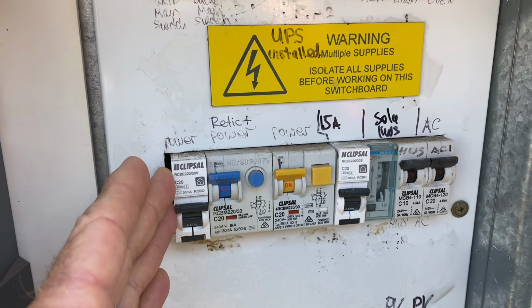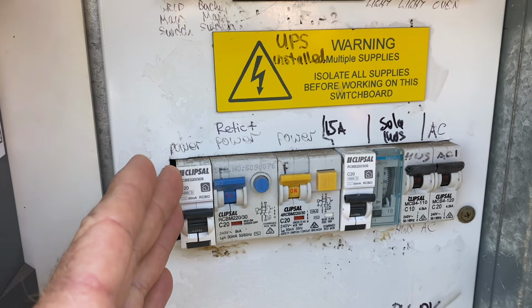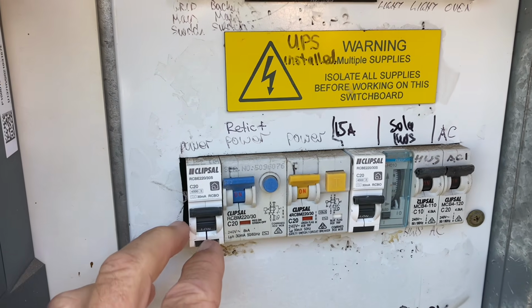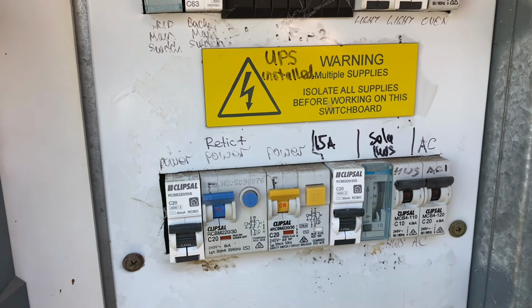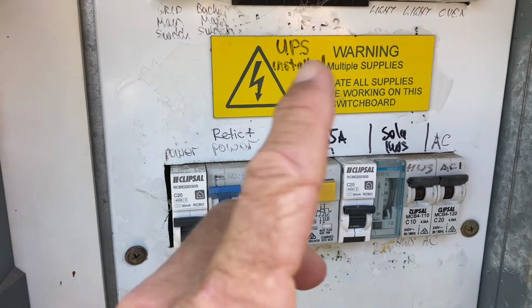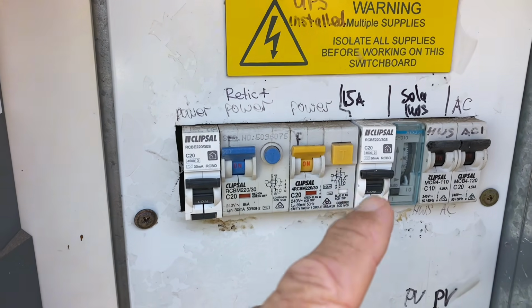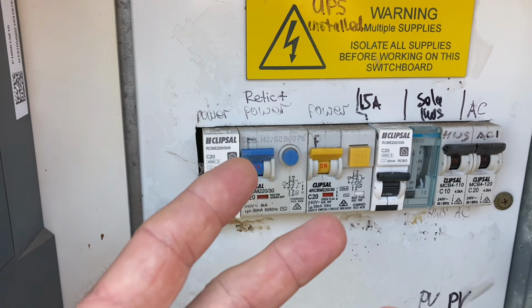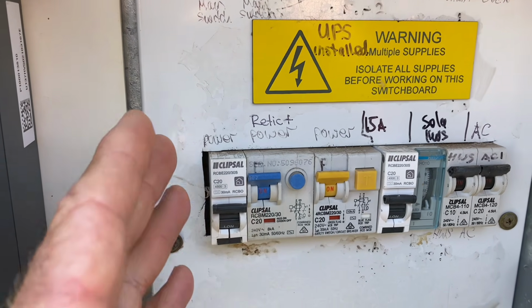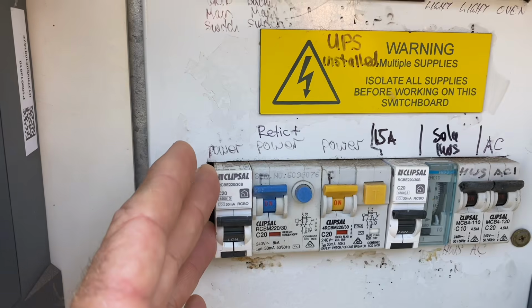If you're in doubt whether they are RCD protected, trip your RCDs, all the ones that you can see, and then go and see if you've got any power to your lights, your power points, all those other circuits, to determine whether they are actually protected by the RCD.